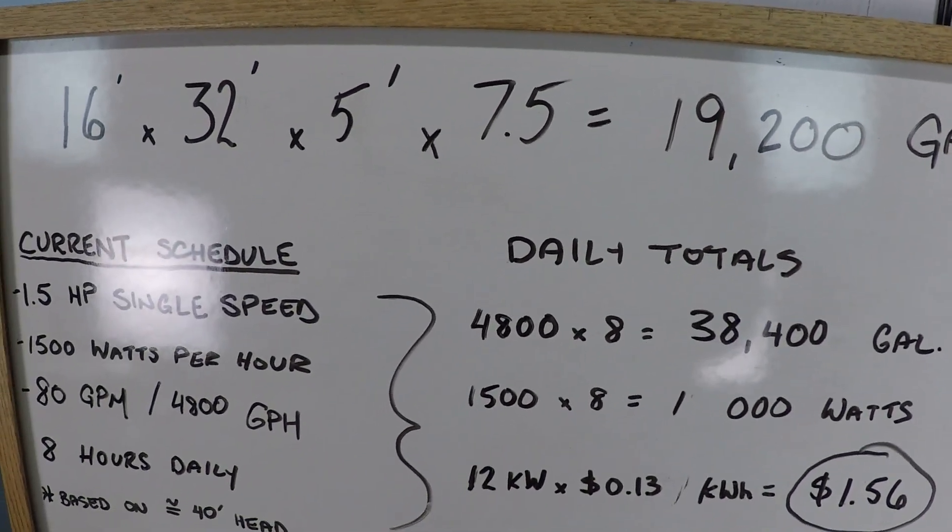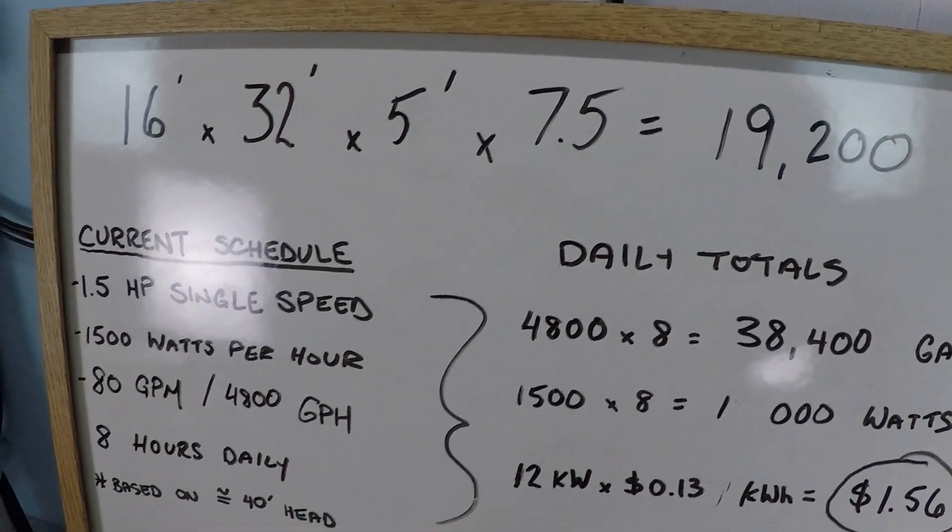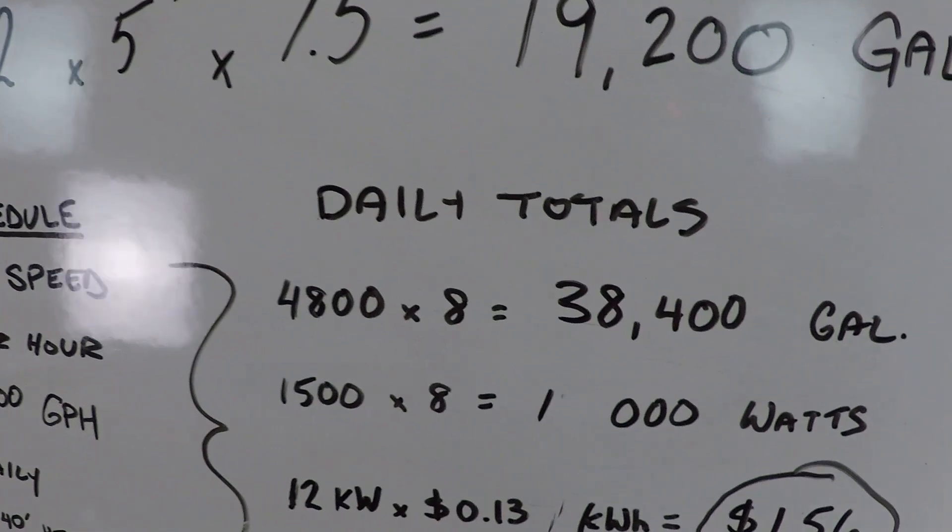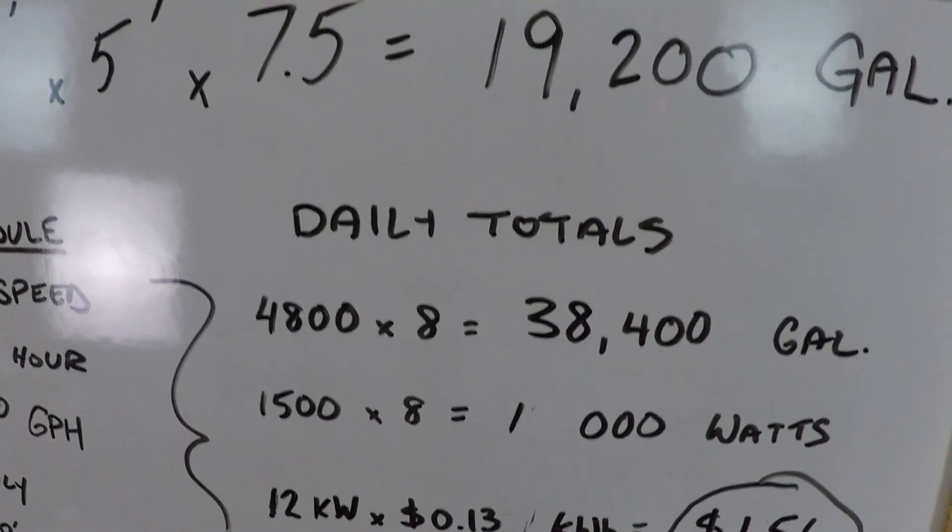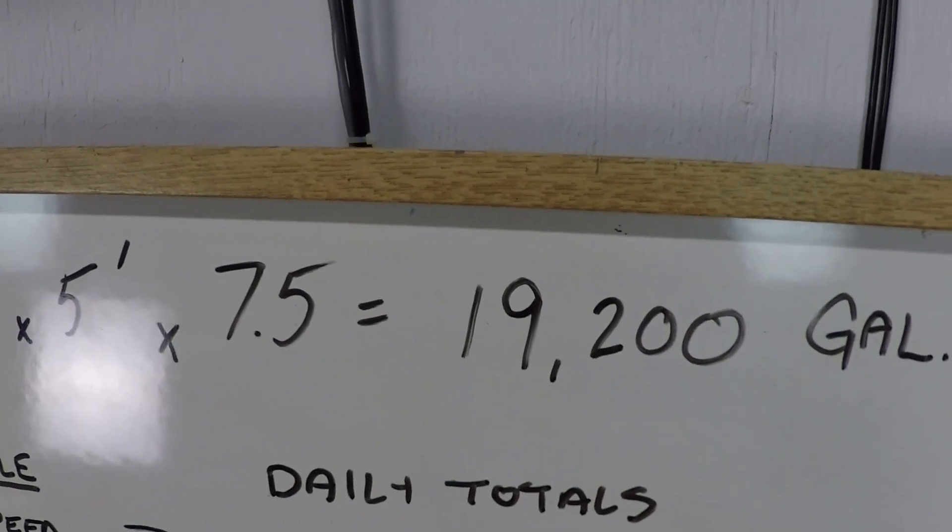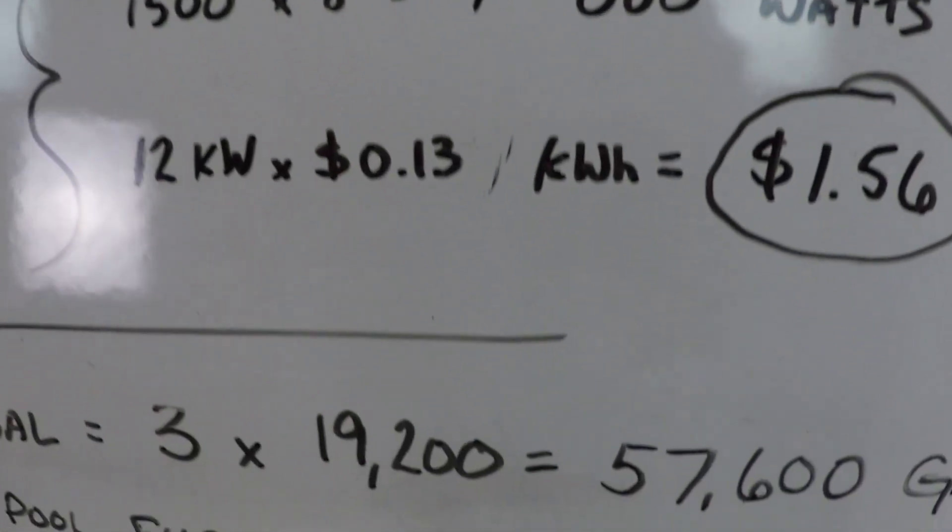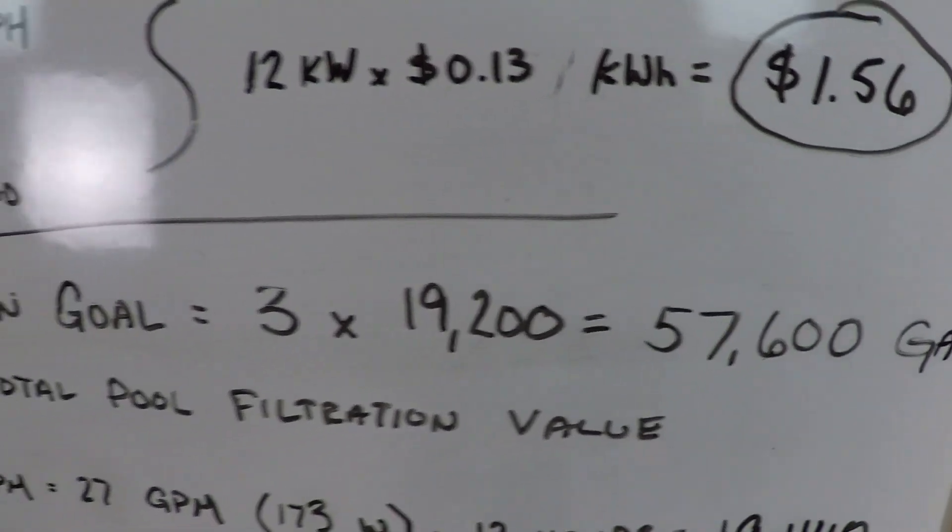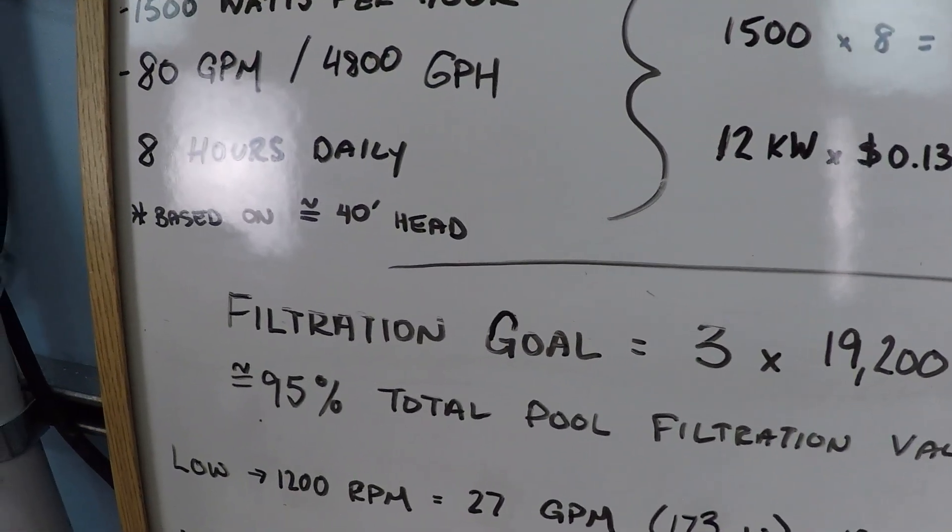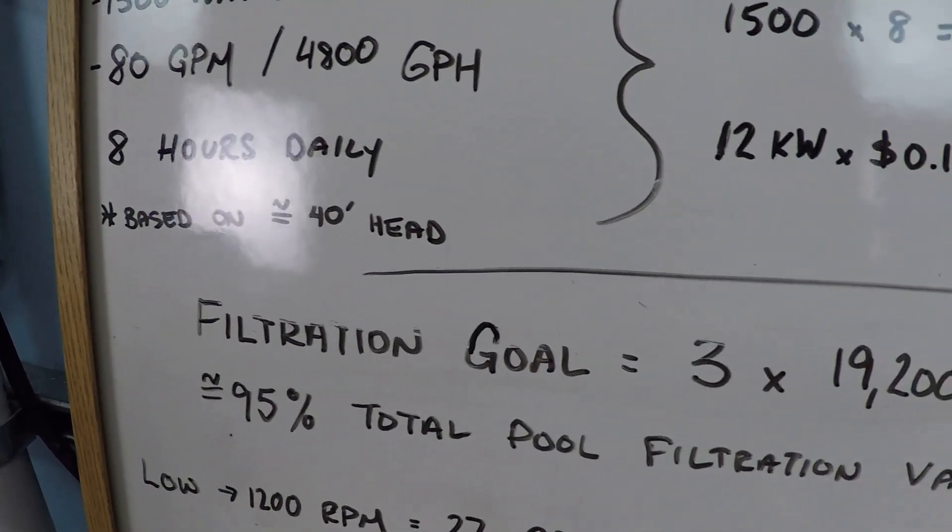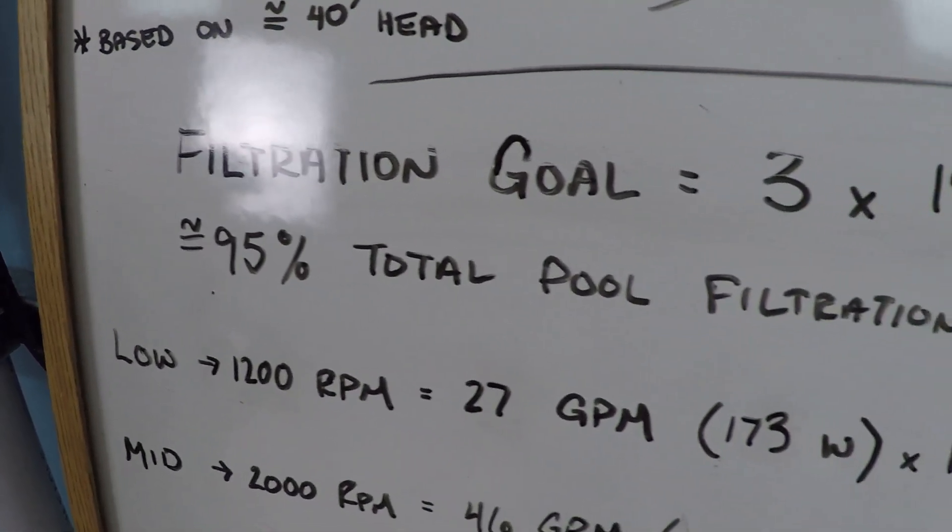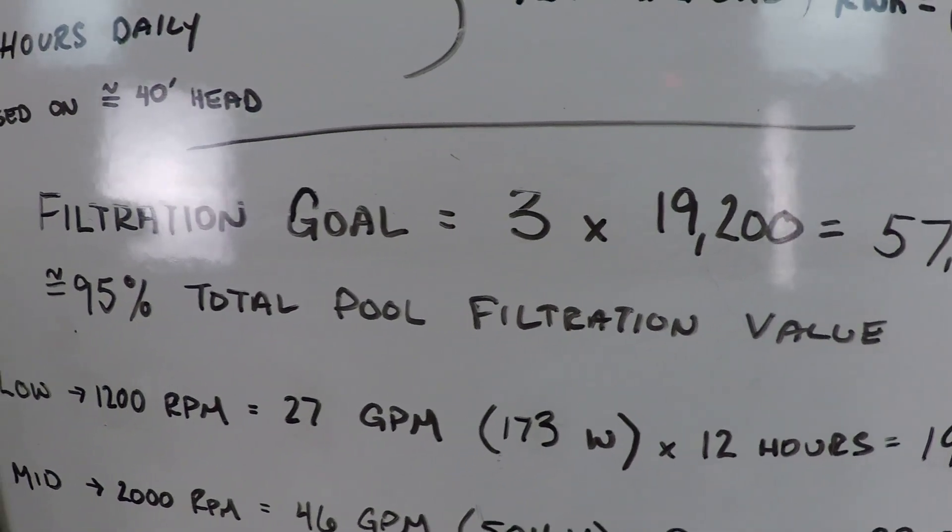I did mention in that video that I would do a follow-up with something that I would consider to be a more optimal variable speed schedule. Basically, instead of having 38,000 gallons daily for this pool, I want to triple this number. So our filtration goal now, 57,600 gallons per day, which should result in approximately 95% of all pool water being filtered at least one time.